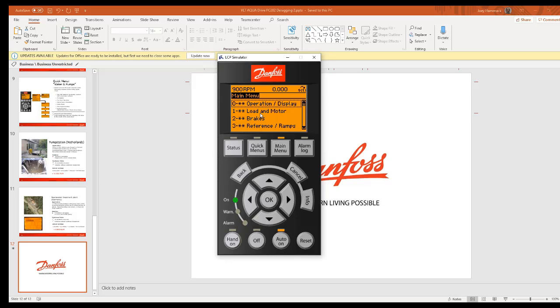This is where we say how many times it will do it. So it can derag and then try to run. If the power goes up and it's still in there, it can do it again, and it can keep doing it up to a limit that we set in the drive. The other site wasn't necessarily rags or towels, it's just that the site has a lot of sediment and debris, and when the pump isn't running, it settles and clogs up the pump. So when you first start, maybe the pump under normal circumstances can power through, and maybe sometimes it can't. So sometimes just running it backwards stirs the sediment up, doing a wig wag like a washing machine, just to get it all moving around, then run forward right out of DERAG. Then the preventative feature was the best choice.